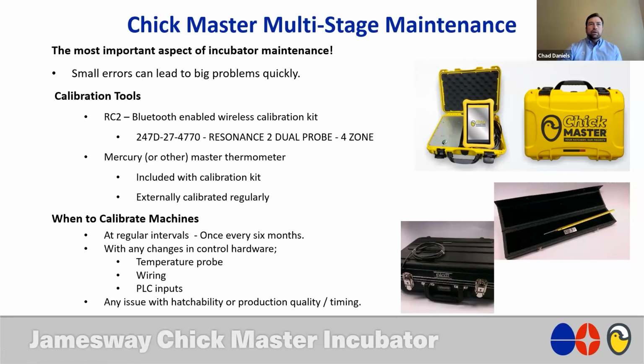And then again, if anything happens, such as if I have to change out a temperature probe, or if there's a wiring issue in the control panel where I have to do some changes, or my PLC input card has failed or anything like that, any of these changes tells me that I probably need to calibrate that machine again, because that will change the voltage that's going to that probe and therefore give you an inconsistent feedback to the PLC to tell it what the actual temperatures are.